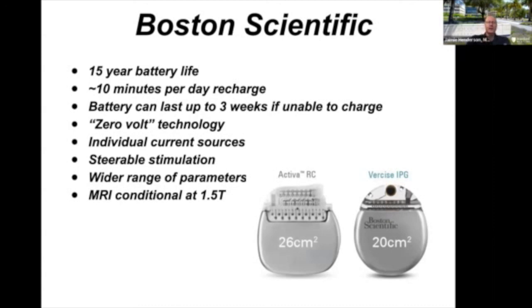One of the things that's impressed me about it is that there are individual current sources. Now, what does this mean? Well, as you saw in the Medtronic lead, there are 4 different contacts on that lead. The Boston lead has 8 contacts, and you can apply electricity to any or all of those contacts. In a system like the Medtronic system, you can pick which ones are on or off, but you can't pick a percentage of how much electricity you'd like to go to that particular contact. You can do that with the Boston one. So it's very finely tunable in terms of the exact location that you want to stimulate.